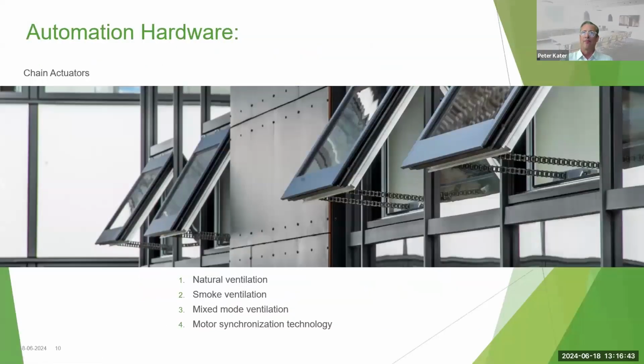The hardware that we use to implement a natural ventilation system in a building, the primary device is called a chain actuator. You can see them here in this image. The chain is housed in a body with a motor in it, which drives the chain in and out of the body, and the chain's attached to the operable sash of the vent, causing it to open and close as the chain moves in and out.